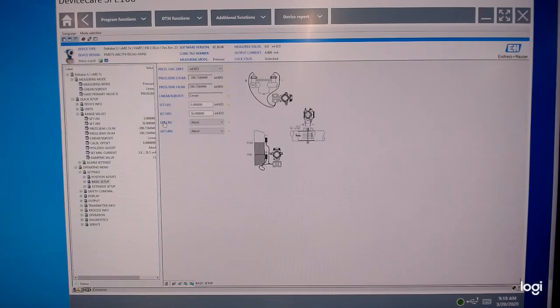Now, different from that is the get LRV and the get URV. Now, this is where we would actually use applied pressure to set those 2 points. This is where we actually recharacterize that sensor. So on the get LRV, if we wanted to use what our actual zero is right now and apply that pressure, we would go ahead and apply pressure to that transmitter. And right now we want 0, so I'm applying 0 right now. Go ahead and confirm that and then hit enter, and it'll lock in the value that's currently being applied. You can see it isn't 0 because it shows up here actually. You can see that it's 0.001476. I mean, we're talking about 1,000th of an inch of water. I mean, it's just nothing there, right?